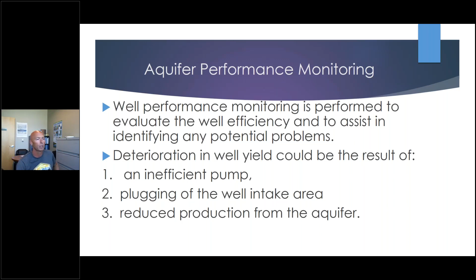To assist in identifying the onset of potential problems, well performance tests can be conducted periodically to determine if there are any changes. So before I carry on, if we have concerns after we do our specific capacity tests after 5 to 10 years, we like to see it closer to 5 years rather than 10, we want to do a well test. We can do a well test with the pump installed, or if the engineer wants to see if that drawdown is really getting bad, we may have to pull out the gear and start with a new pump.